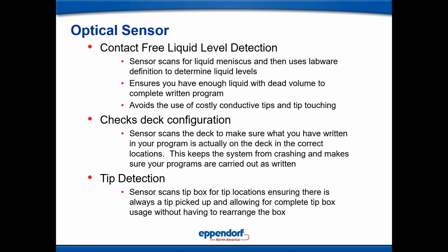Whereas with most machines, you would not trust that. You would simply have to change out your tips every single time you go into the well. With our machine, you can be sure that the machine will stay away from the liquid that's already there. And it does back up as it dispenses to stay away from the rising liquid levels, and also drops down as it aspirates to keep pace with falling liquid levels in the aspiration stroke. So this is a widely important feature that is simply not available on most workstations. It tells you before you walk away from the machine whether you have enough liquid, and it even keeps track of the dead volume and mixing volumes and all of those things, so it knows whether the machine can do what you've asked it to do.